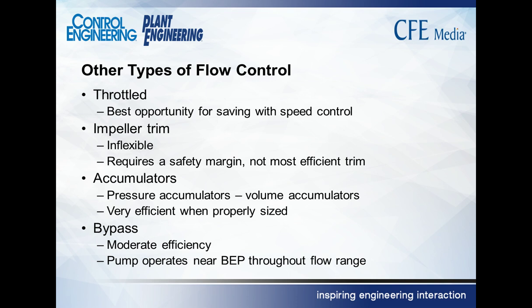So there are other things you can do to control flow. We talked about throttling and we talked about trimming speed. As we said early in the presentation, you can also trim the impeller. And trimming the impeller will have just about the same effect as reducing the speed, but I can't run the lathe backwards and put the metal back on the impeller. Once you trim the impeller, it can't go bigger without replacing it. So if you've got applications where you need to control the flow rather than just achieve a lower flow rate, a variable speed drive is an answer.